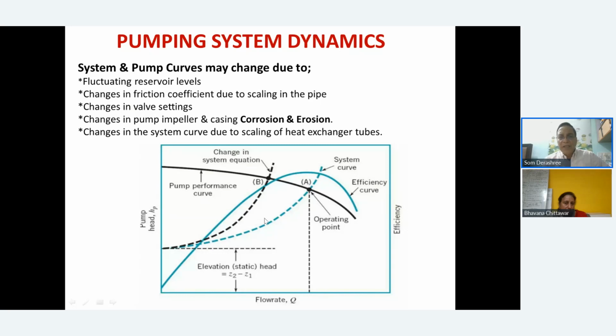As you keep closing the valve, the system curve will keep bending till it goes vertical here, when you have totally shut off the valve. This will be the point when you have shut off the discharge valve and the pump is still running. So the pump curve goes like this, all valves are open. This is the point at which it cuts. This is the operating point. This is where it will operate. There is no choice. It has to operate at this particular point.